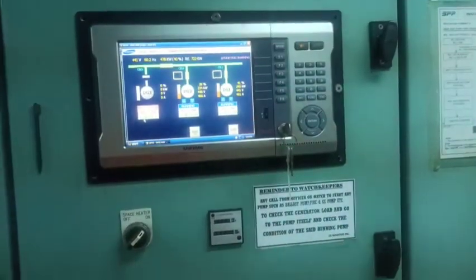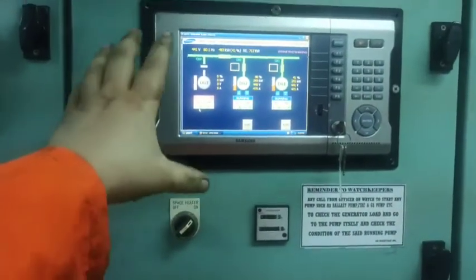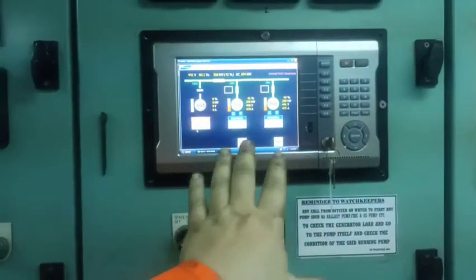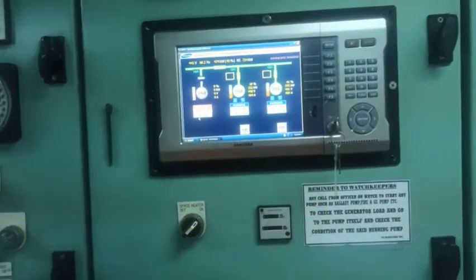You unload, you adjust a little bit, you load again. Do not try, when you have two diesel generators on load, to touch the AVR. You will make a serious trip.